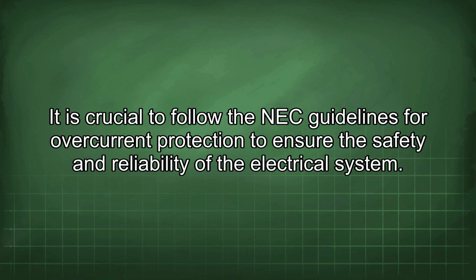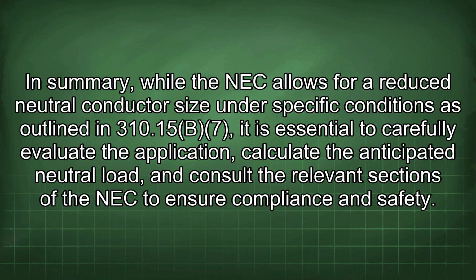In summary, while the NEC allows for a reduced neutral conductor size under specific conditions as outlined in 310.15(B)(7), it is essential to carefully evaluate the application, calculate the anticipated neutral load, and consult the relevant sections of the NEC to ensure compliance and safety.